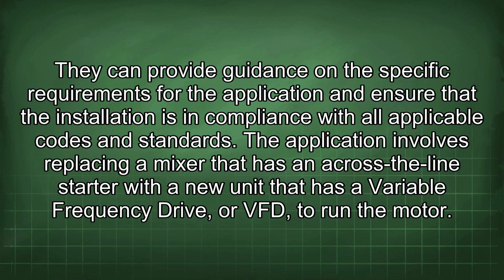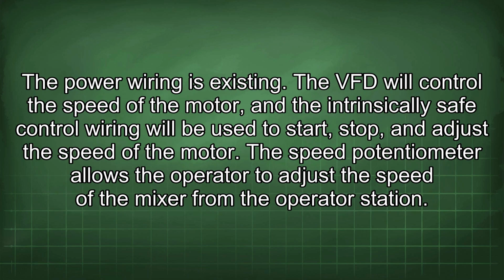The application involves replacing a mixer that has an across-the-line starter with a new unit that has a variable frequency drive, or VFD, to run the motor. The power wiring is existing. The VFD will control the speed of the motor, and the intrinsically safe control wiring will be used to start, stop, and adjust the speed of the motor.